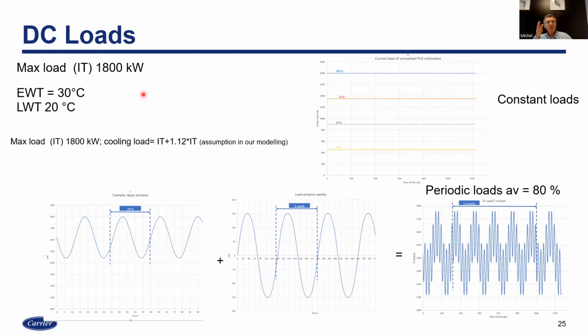In other terms, you can say a data center is always loaded. What does that mean? Let's see what happens if I have constant load across the year, 100% load. For instance, if it's 1800 kW across the year, it may be 75% load, or 50%, or 30%. Usually people ask for data at 100% load across the year, and what the PUE or average efficiency would be at 75% or 50%.